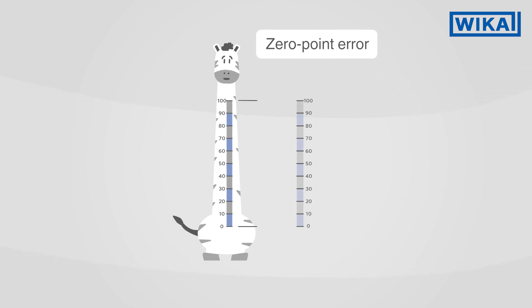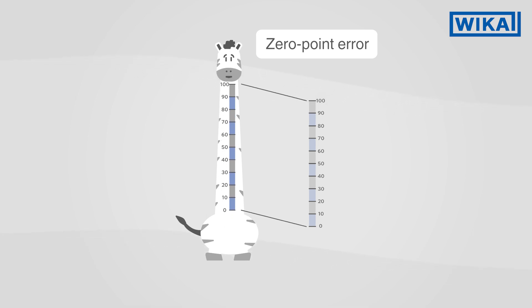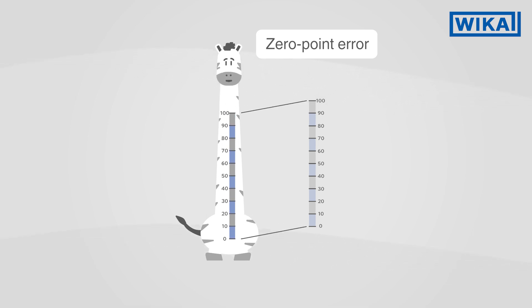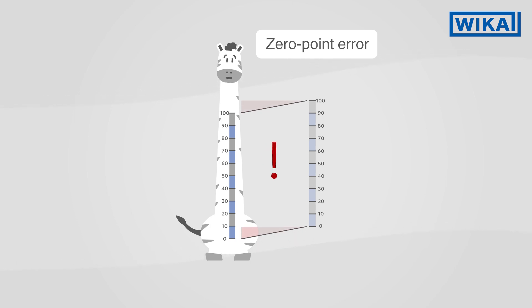The zero point error describes the deviation of the start of the measuring range from its set value. It arises when the chart has been set too high or too low. As a result, the whole scale shifts and all the measuring results will deviate from the actual value by exactly this value.